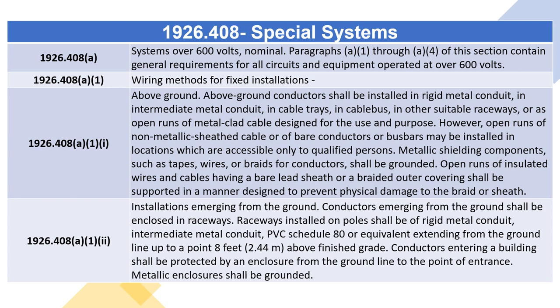1926.408(A)(1)(ii) — Installations Emerging from the Ground. Conductors emerging from the ground shall be enclosed in raceways. Raceways installed on poles shall be of rigid metal conduit, intermediate metal conduit, PVC schedule 80 or equivalent, extending from the ground line up to a point 8 feet (2.44 meters) above finished grade. Conductors entering a building shall be protected by an enclosure from the ground line to the point of entrance.